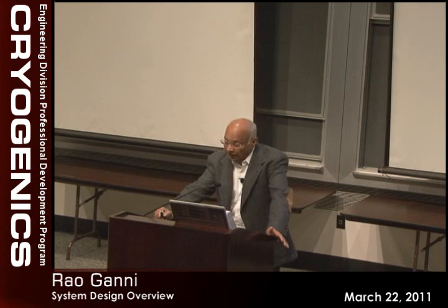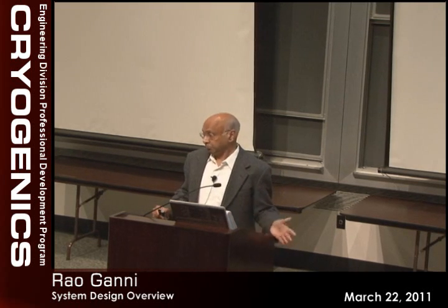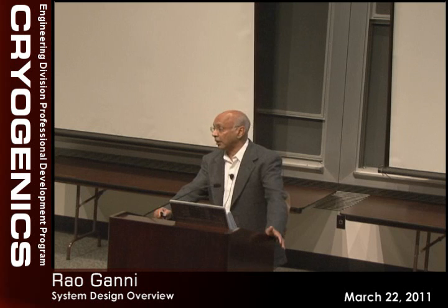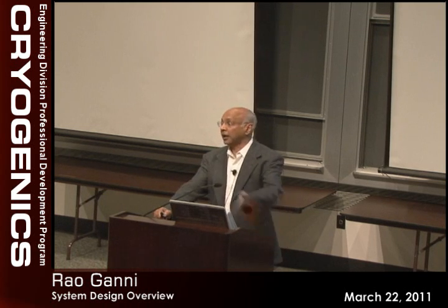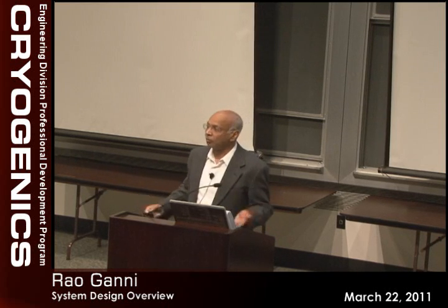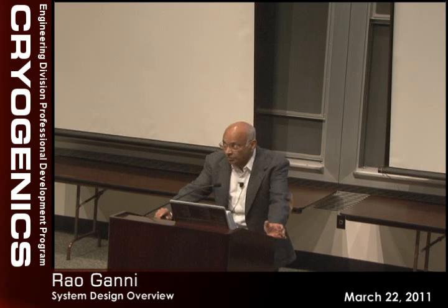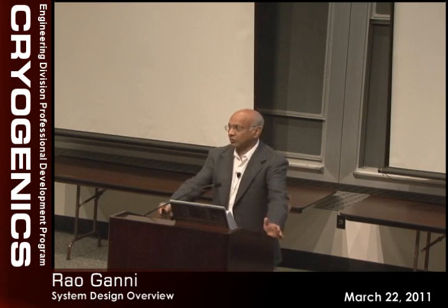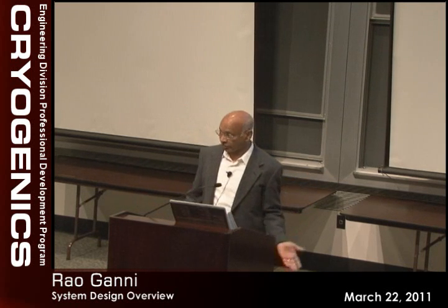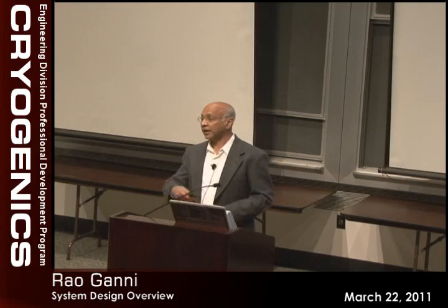But in other places, as I said at the beginning about component selection, at 20 atmospheres at normal room temperature you are allowed to use 150 pound flanges, which are rated up to 280 pounds or 20 atmospheres. But if you cross that boundary, say to 22 atmospheres, you are now stuck with 300 pound flanges. Just because somebody doing the cycle analysis is only concentrating on thermodynamics and not paying attention, which has happened many times, like our CHL being designed for 22 atmospheres, that added so many extra heavy flanges on the system, and it carries through.